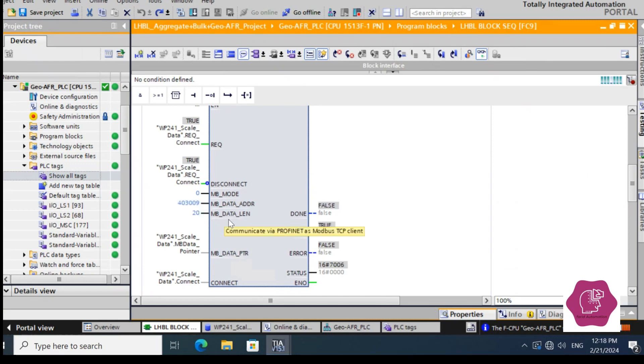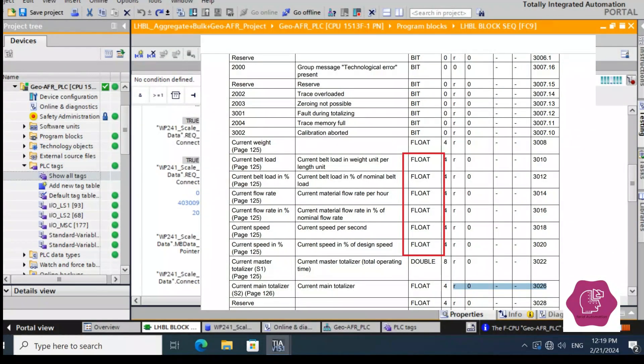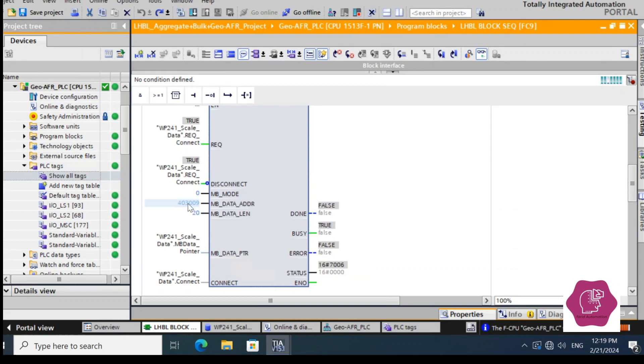We are taking 20 holding registers, so MB_DATA_LEN is 20, which means 10 double words — and each double word holds 1 data value. Because our data is a float (4-byte data), one double word equals 4 bytes. And this is MB_DATA_PTR: you have to give a data pointer or any data area to store the data read from those holding registers.